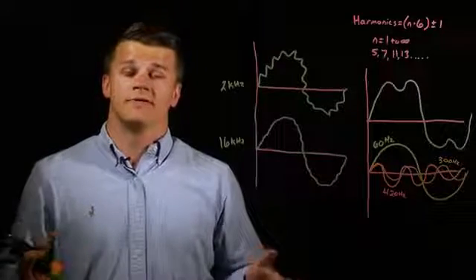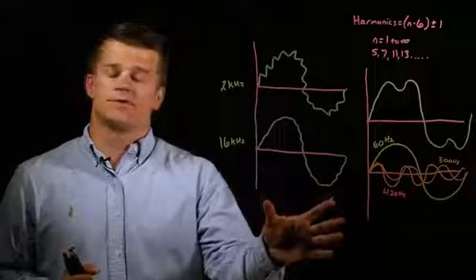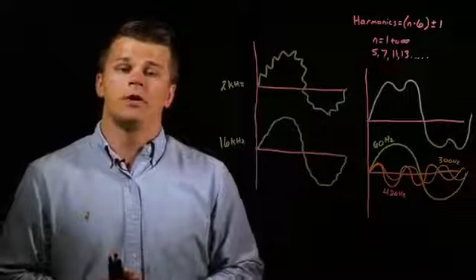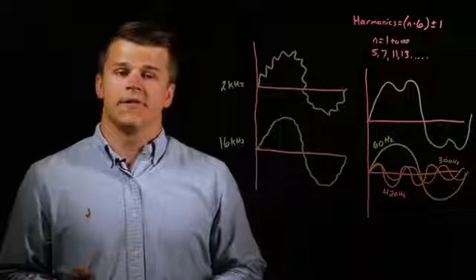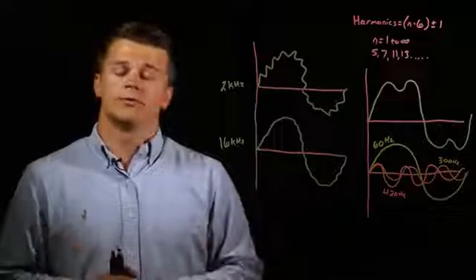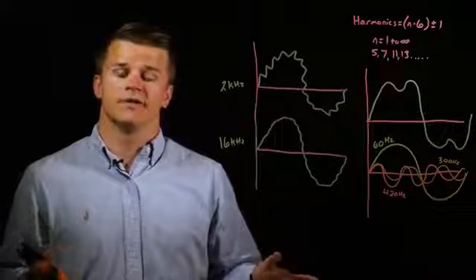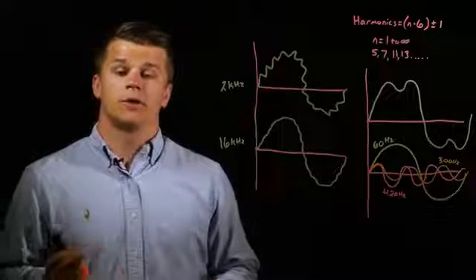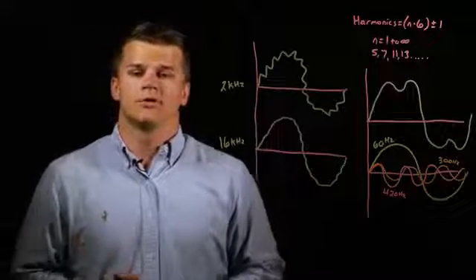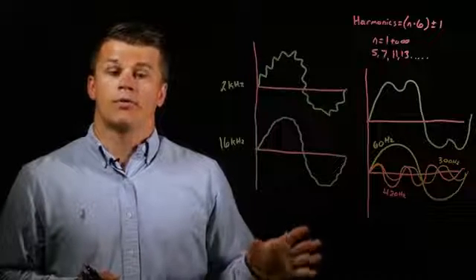Then there are a lot of advantages that come with increasing the switching frequency. The biggest of those is because you have this cleaner output waveform, you'll have lower motor losses and thus a higher efficiency in your motor. And then this output waveform will also allow for lower motor heating, which can increase the lifetime of your motor and will produce lower audible motor noises. So in applications such as in the theater industry, you'd have a quieter motor operation.